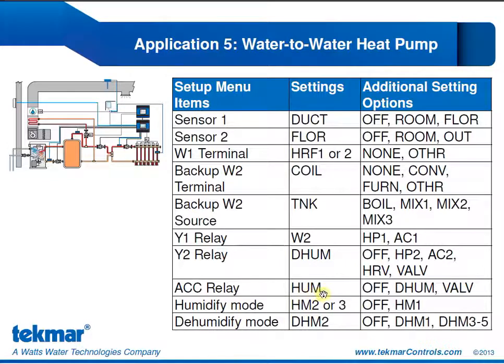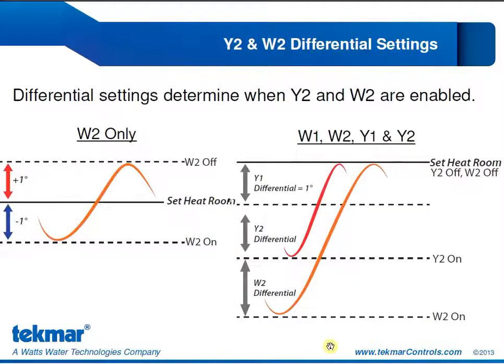Our Y1 relay is going to be configured for W2 because our first stage of cooling is that fan coil. Our Y2 relay will be configured for dehumidification. Our accessory relay configured for the humidifier operation. Because that humidifier is in the ductwork, that is humidify mode 2 or 3, and our dehumidification mode is 2 for the coil operation.